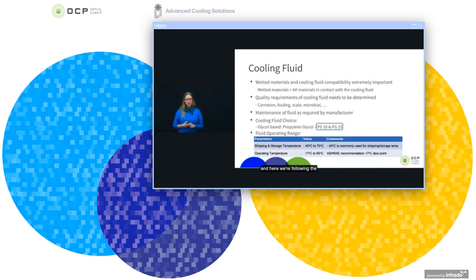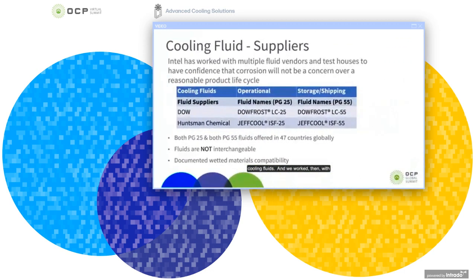And here we're following the ASHRAE recommendation of not going below 17 Celsius to avoid condensation within the IT equipment itself. So that's what we've been doing when it comes to cooling fluids. And we worked with multiple fluid vendors and test houses to make sure that we don't see any corrosion issues when it comes to these liquids and wetted materials.